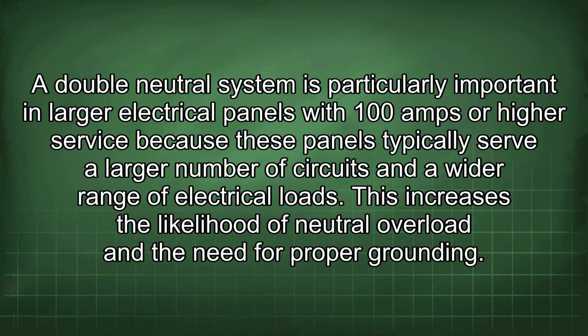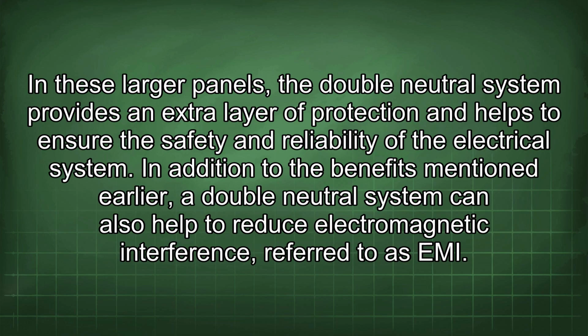A double neutral system is particularly important in larger electrical panels with 100 amps or higher service because these panels typically serve a larger number of circuits and a wider range of electrical loads. This increases the likelihood of neutral overload and the need for proper grounding. In these larger panels, the double neutral system provides an extra layer of protection and helps to ensure the safety and reliability of the electrical system.